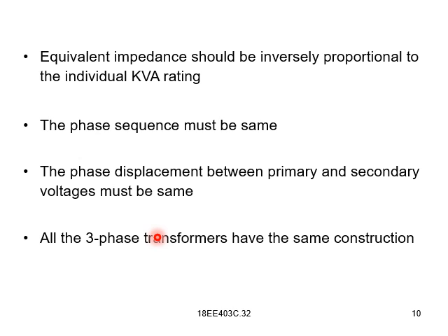The thing is, equivalent impedance should be inversely proportional to the individual kVA rating. The phase sequence must be same. The phase displacement between primary and secondary voltages must be same, and all the three phase transformers have the same construction.